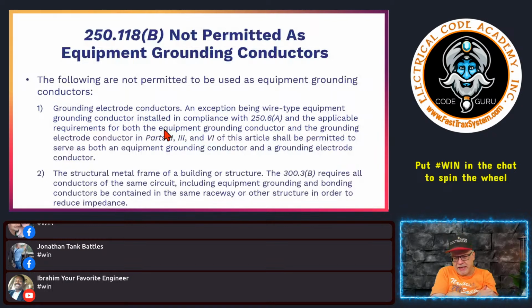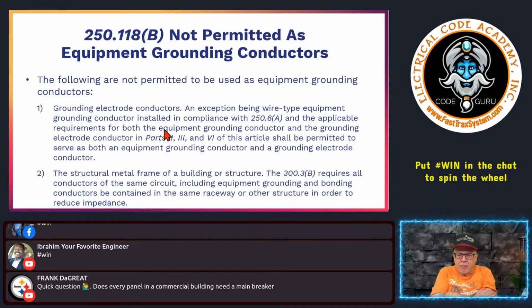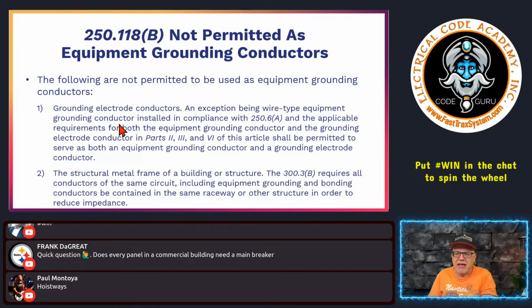Now let's talk about what cannot be an equipment grounding conductor. Okay, we get this question an awful lot. So what cannot be qualified or is not permitted to be used as an equipment grounding conductor? Okay, so the following. The first one says the grounding electrode conductor. So this is a general statement because there is an exception. Okay, so generally, an equipment grounding conductor, a grounding electrode conductor, I should have said that. A grounding electrode conductor, GEC, cannot be used as an equipment grounding conductor. That's a general statement, okay?